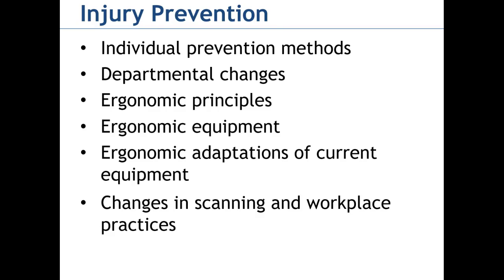So there are ergonomic equipment measures that we need to think about, and the equipment manufacturers have become very in tune to the need to have really ergonomic pieces of equipment, where the monitor can be moved independent of the control station, and the control station or control panel is independent of the monitor, so these can be moved, tilted, lowered, raised, and so forth.